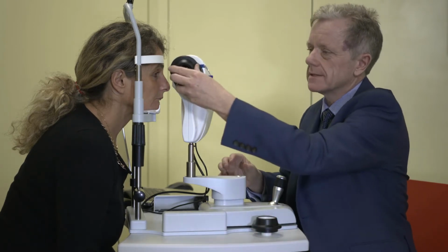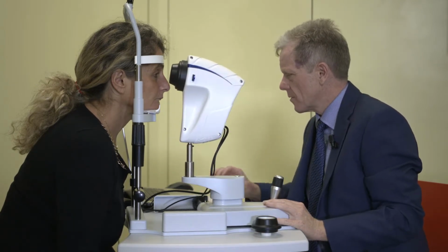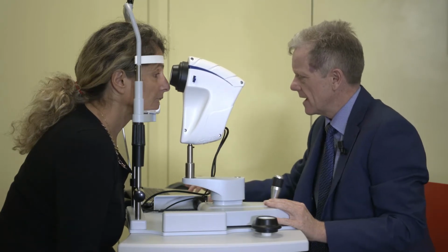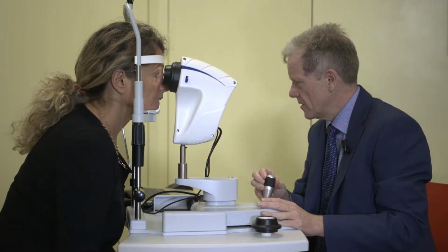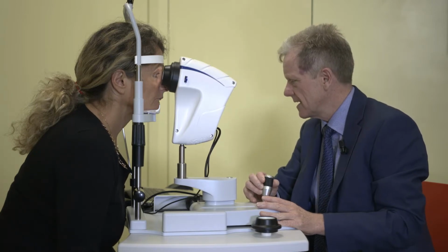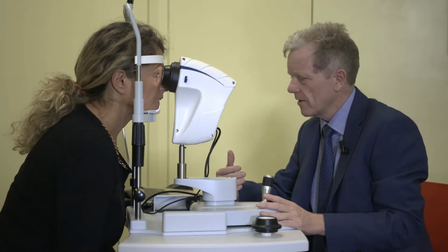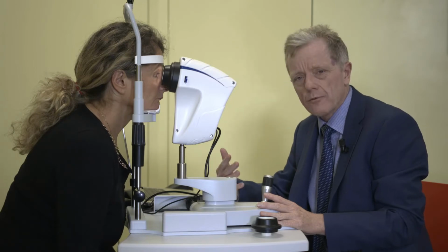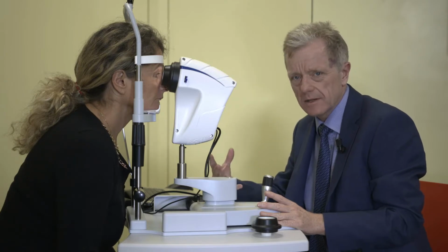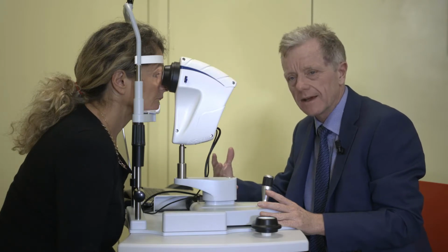So it's quite easy to put these cones on the front of the device and then just with the device look at obtaining some of the images. So here we have a laptop that just allows us to focus. And here I have the Placido disc looking at that quality of the tears, and we can see breakup time. Simply I start a video, and the video itself will record the blinks and the breakup of the tear film during the course of a normal blink routine. So no instructions to the patient, just a normal blink, and then just analyzing that tear surface.